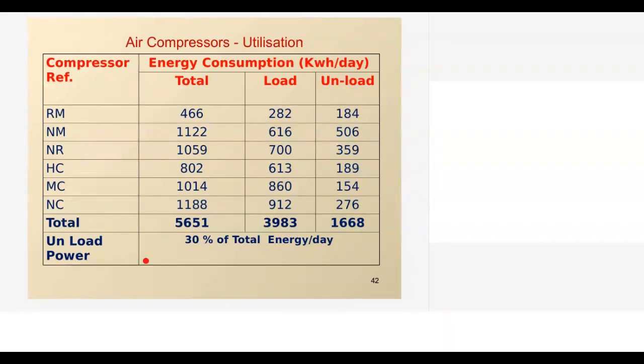This is again a large engineering network. More than 7-8 compressors were there. Each department has a separate compressor station. When we did the audit, we took how much power is consumed at load, and how much is consumed at unload. If you take all the compressors put together, unload power is 30% of the total compressor energy.